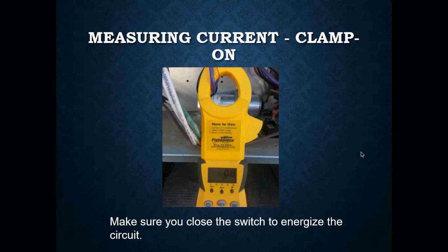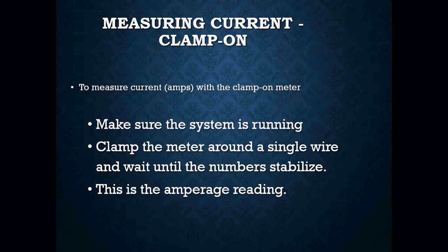Okay, so here is your clamp-on meter. So you got to make sure you close the switch to energize the circuit in order to get an amperage reading, because remember, amperage is also a byproduct of the electrons moving, so we have to have power on in order for us to get an amperage reading on a particular piece of equipment.